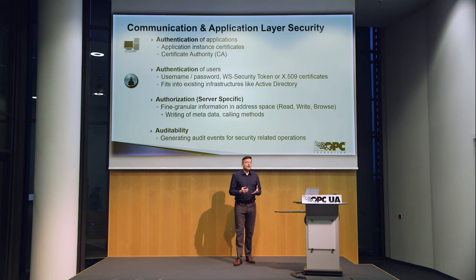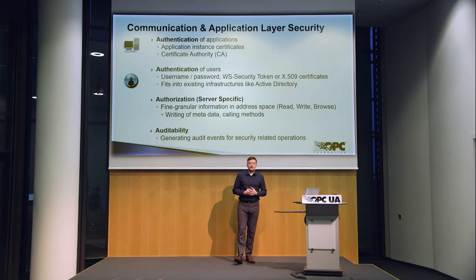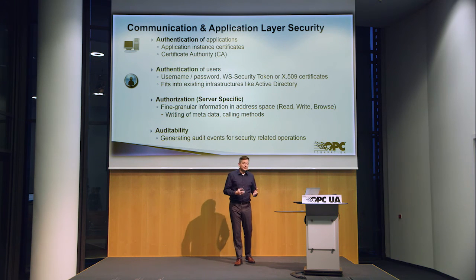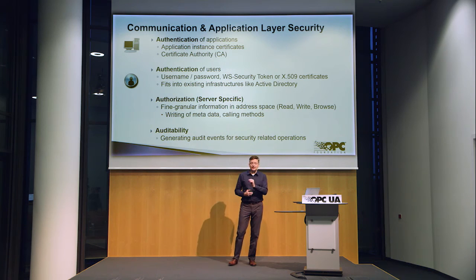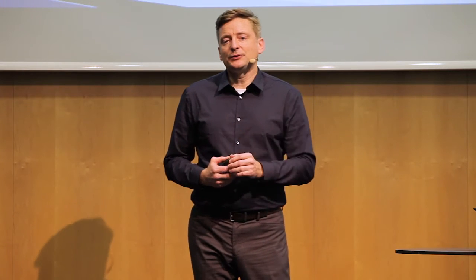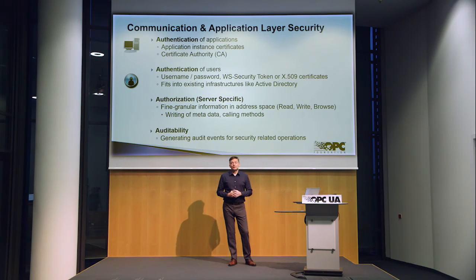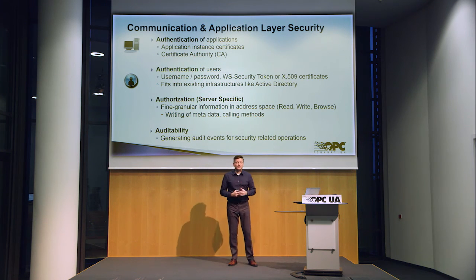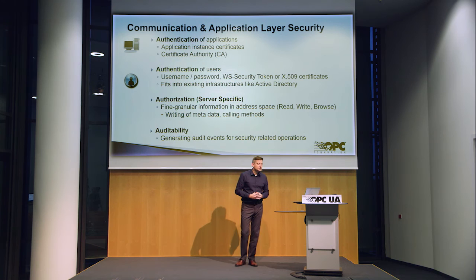Now, depending on how well an OPC UA server is written, that may be all or nothing type control, or it might be very precise and tied down to allow you to determine whether you're allowed to do each individual function on each individual tag, or per user per tag type security. Okay, and that just depends on what's required and how the vendor implements the UA server. But the specification provides all the tools that are required for vendors to write very controlled, secure OPC UA servers.